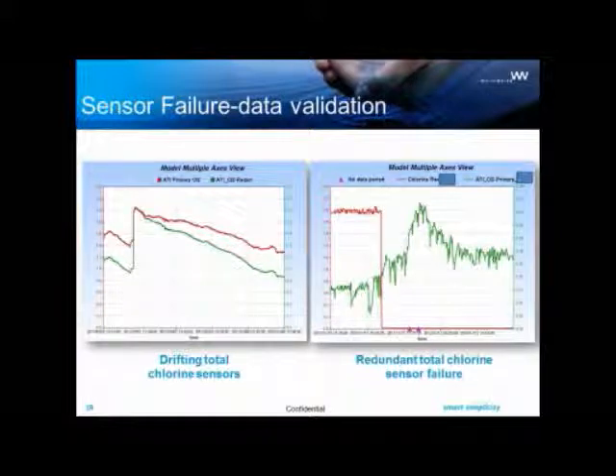Okay, and again, going back to sensor failure and data validation. What you see here on the left side is a drifting total chlorine sensor, and on the right side you can see a sensor failure. Both of them are total chlorine, and we are issuing an alarm saying, hey, what you have right now is a sensor malfunction and not a problem in your water quality. So first of all, you know as the operator that right now you have a problem that you need to face, a sensor that is drifting or malfunctioning, but in addition, this is not an event that you would count as a water quality event.